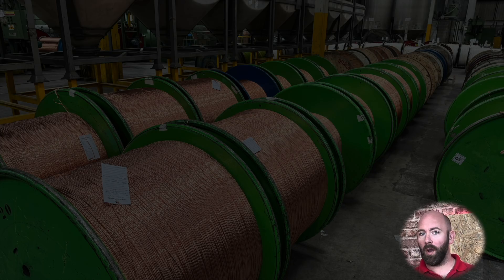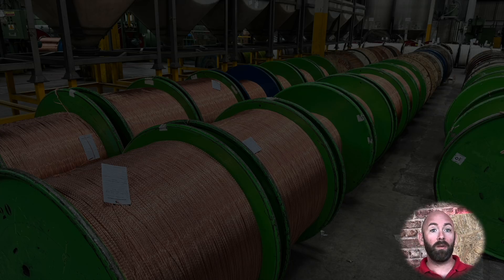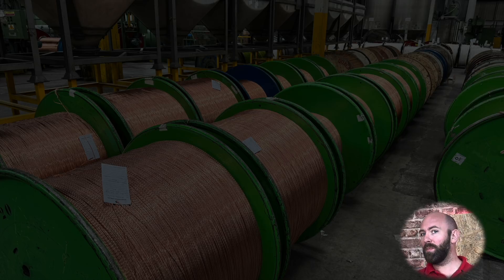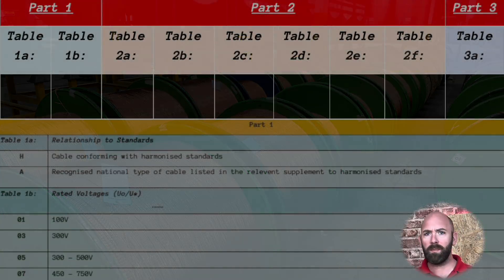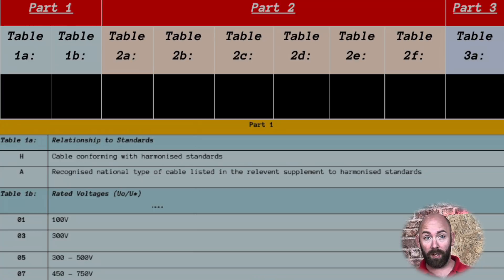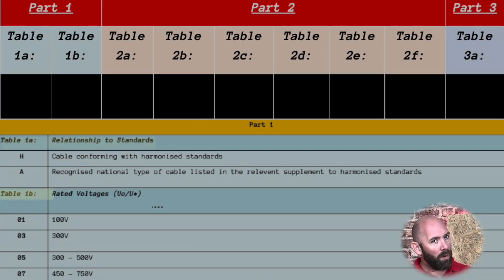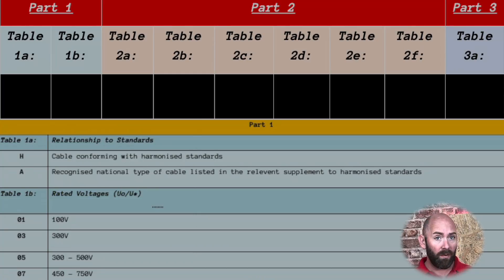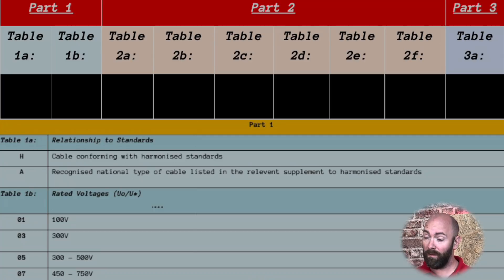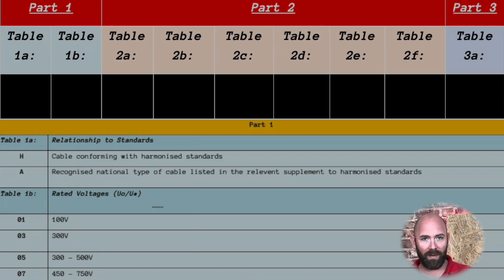In these boxes we're going to put our code and they are broken up into three parts, and we're going to use the harmonized cable code table to navigate and identify this cable code. Part one is broken up into two subsections. One A indicates the relationship with the standard the cable has — is it harmonized or is it part of a national standard? One B indicates the rated voltage of the cable, starting with 01 as 100 volts, 03 as 300 volts, 05 as a voltage range of 300 to 500 volts, and finally 07 which is 450 to 750 volts.